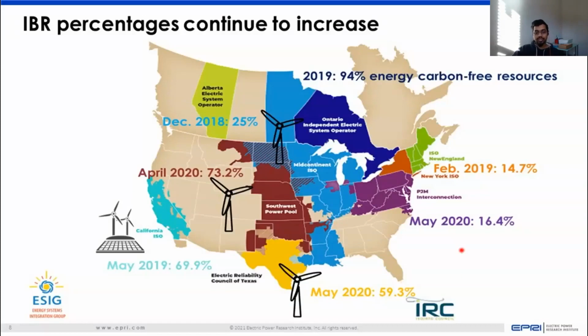There can be situations where pockets of a system hit 100% instantaneous penetration in energy delivered from inverter-based resources for a few hours of the day. That is the kind of situation we want to immediately address with respect to frequency control, because if an event occurs in the system at that point, that's something we need to be ready for and prepared for as we start hitting these percentages more often nowadays.